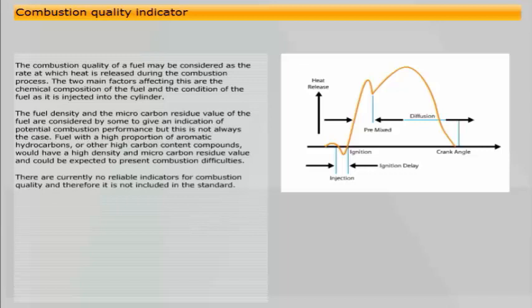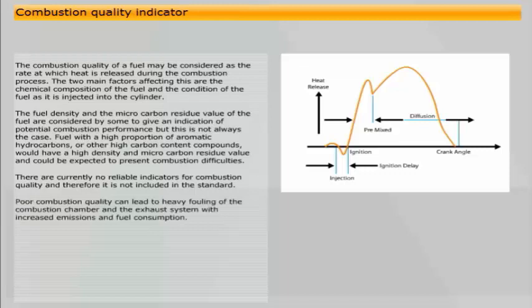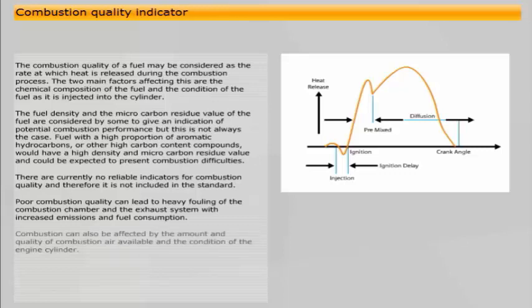Poor combustion quality can lead to heavy fouling of the combustion chamber and the exhaust system, with increased emissions and fuel consumption. Combustion can also be affected by the amount and quality of combustion air available and the condition of the engine cylinder.